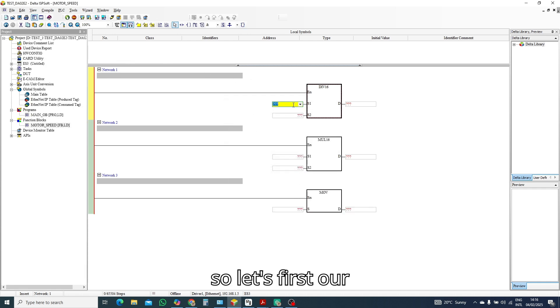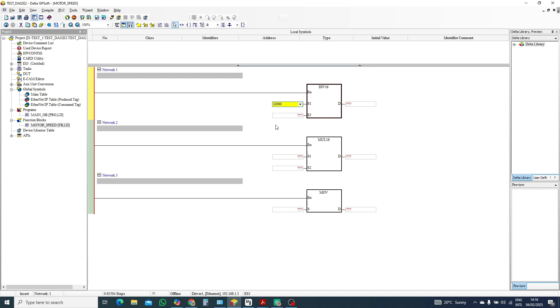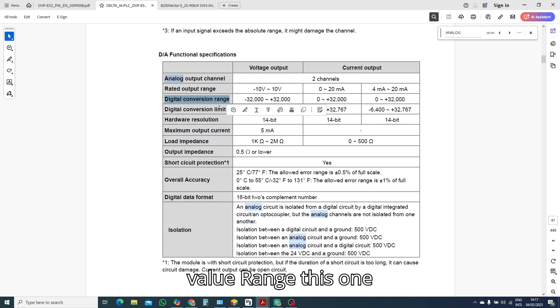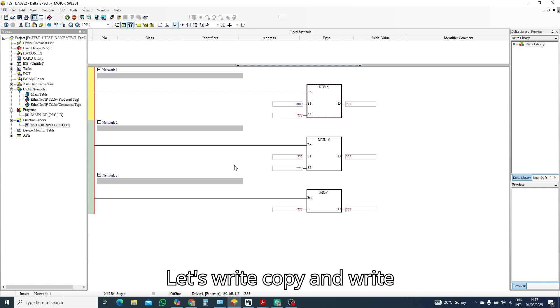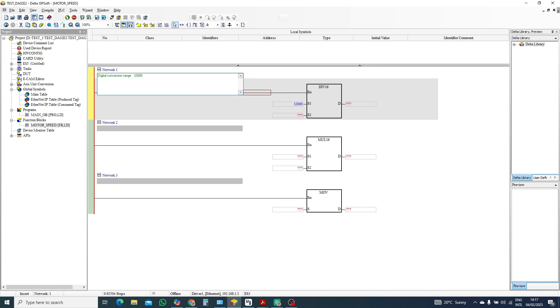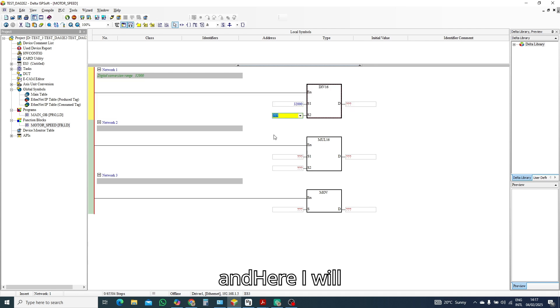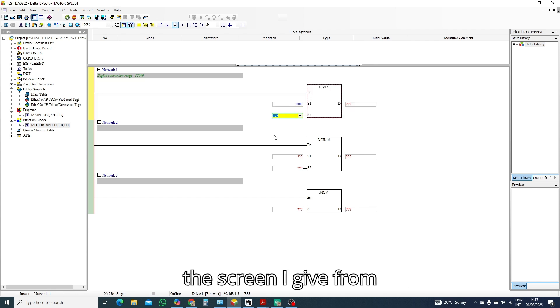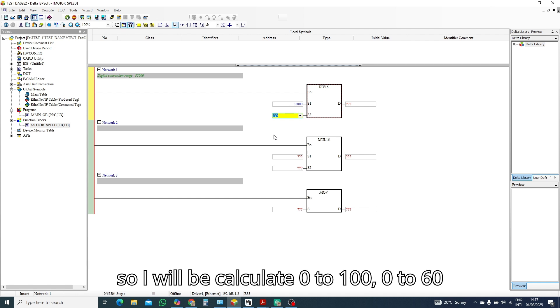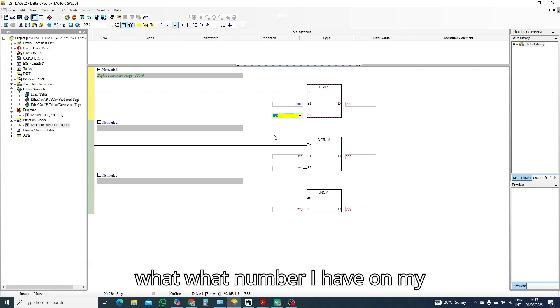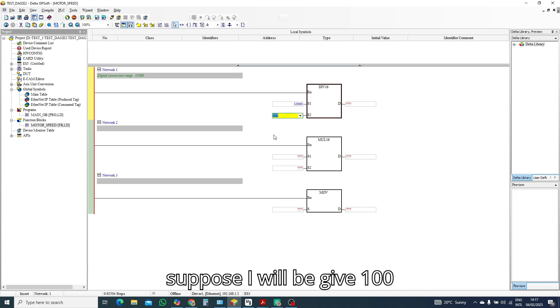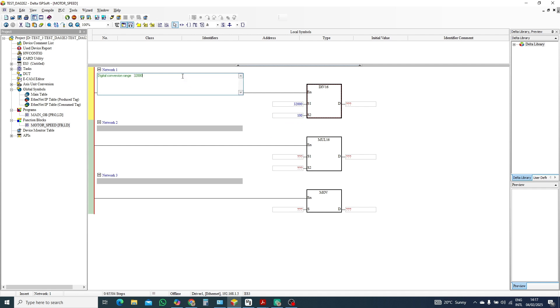So let's first our value is 32,000, this is our digital conversion value range, this one. Let's copy and write here because I will be remembering. And here I will give my maximum value on the screen. I give from suppose 0 to 60, 60 hertz. So I will calculate 0 to 100, 0 to 60. What number I have on my PLC maximum rate, I will write here. Suppose I will give 100.